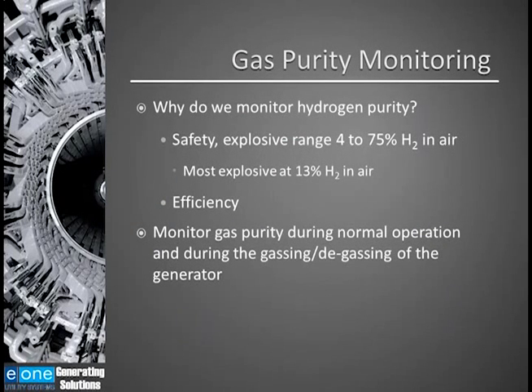Why do we measure the gas purity? I believe the number 1 reason is safety. Hydrogen has a very explosive range. Between 4 to 75% hydrogen when mixed with air is explosive. The most explosive range is around 13% hydrogen in air. We also monitor the hydrogen purity for efficiency. The purer the hydrogen in the generator, the less windage losses you have, the easier you can spin the rotor, the more megawatts you can produce. So we're measuring hydrogen purity for both safety and efficiency.